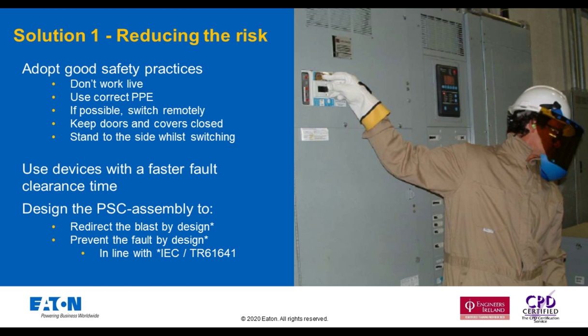Other good practices are standing clear and the to-the-side stance, as shown in the picture. If there is a fault, in this particular instance where the toggle of the moulded case circuit breaker is at the front of the switchboard, you will get some exhaust of ionised gases coming from around the handle area of the circuit breaker. So it's a good stance to adopt to minimise any arc flash damage that one potentially could get.